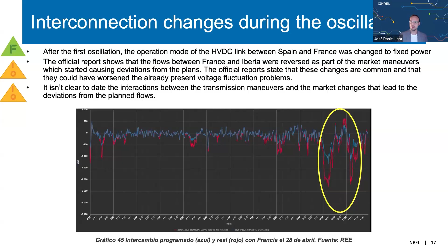So 12 minutes before the oscillation of the generation trip, now we have this voltage data, which we didn't have. The community didn't have this data prior, like when the event first happened. And here's where you can actually see that as soon as the operator starts taking these maneuvers, the voltage starts to rise, and it starts to rise quite significantly. And the frequency also starts kind of staying still.